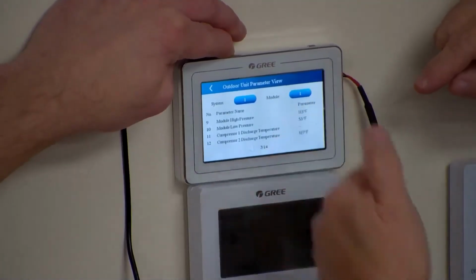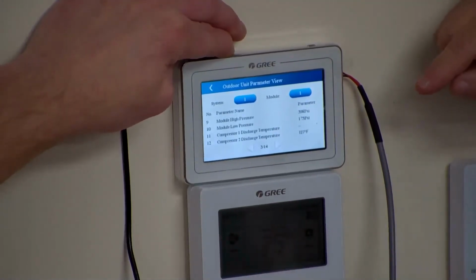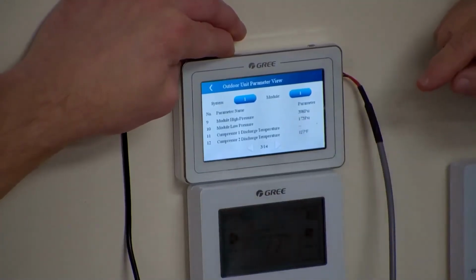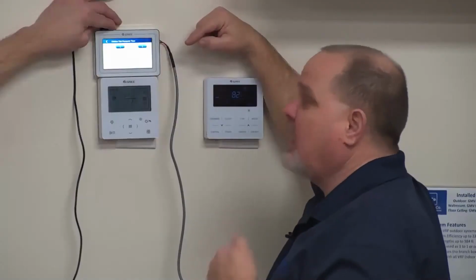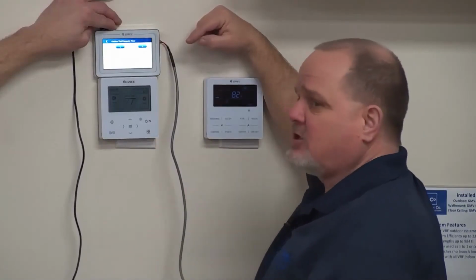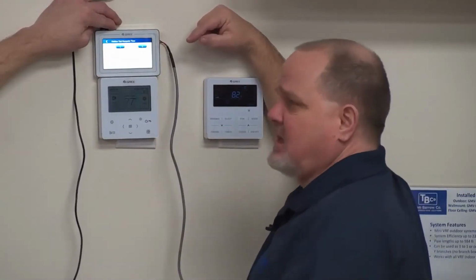So I'm running 400 or 398 psi of head pressure and 173 pound back pressure. Makes sense to me when it's 68 degree ambient, right? You wouldn't be seeing suction pressure that high if you were in a much colder environment. You would probably still see that head pressure because the thing's trying to build that head pressure so we get that discharge temperature, so we get to release that heat.